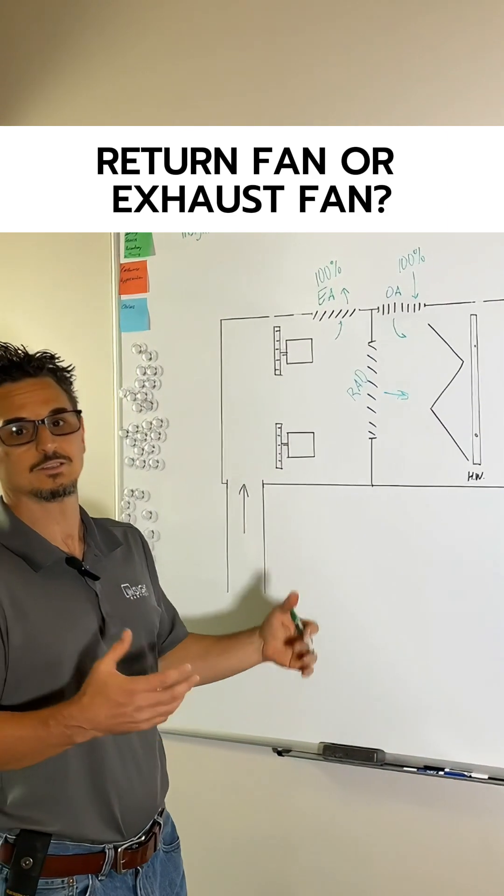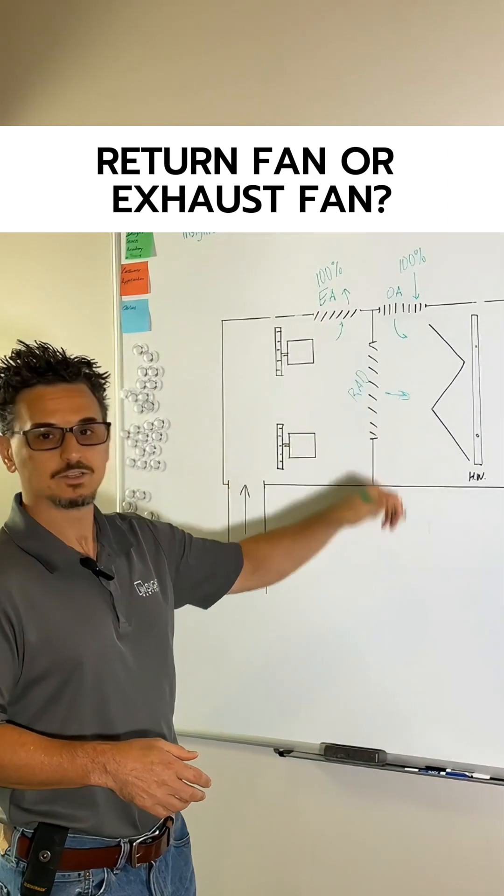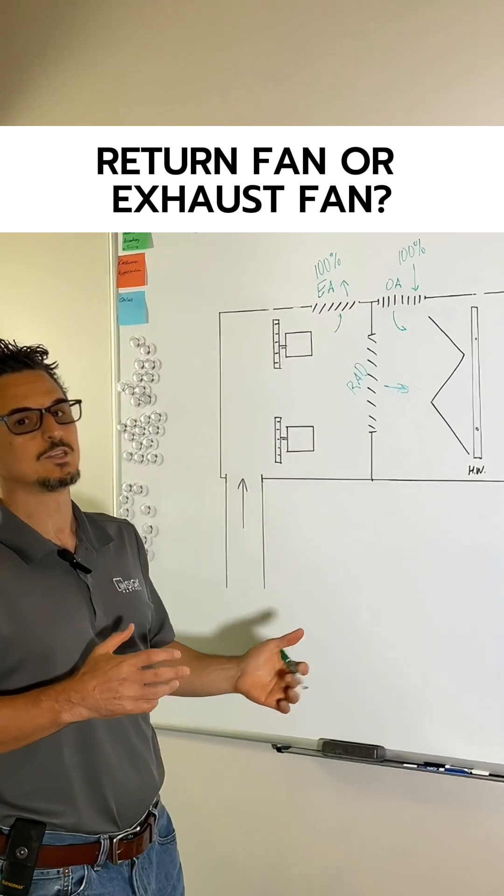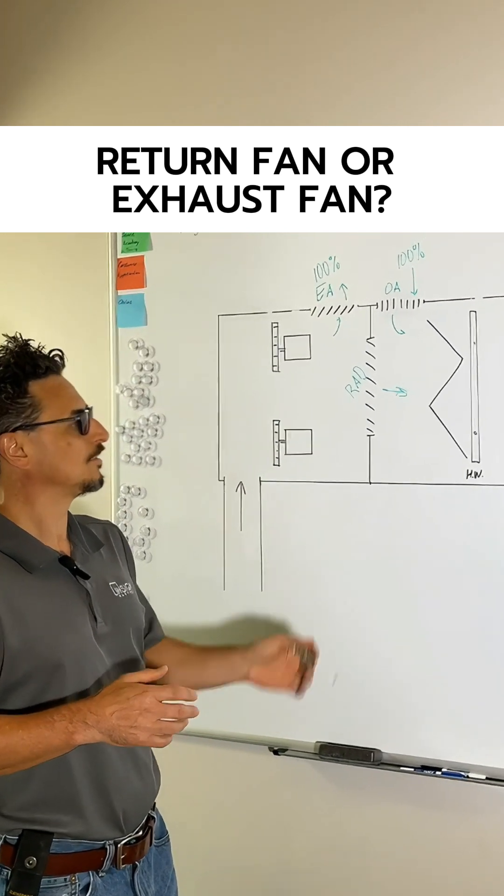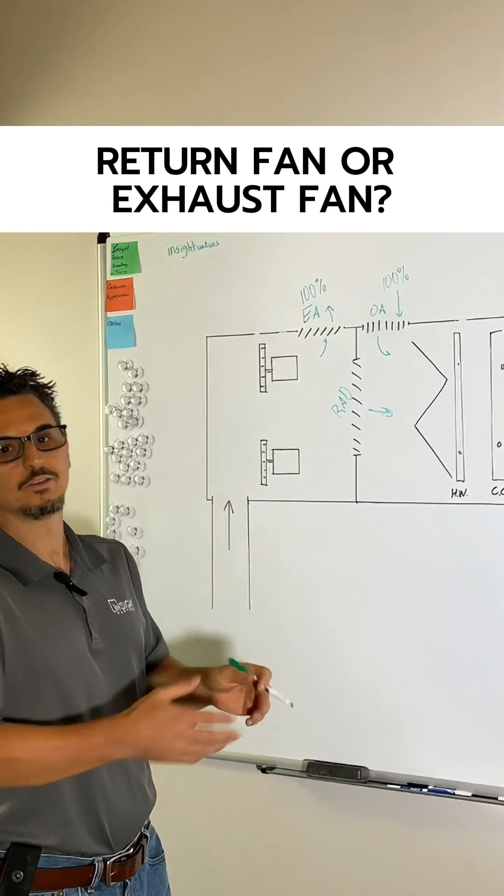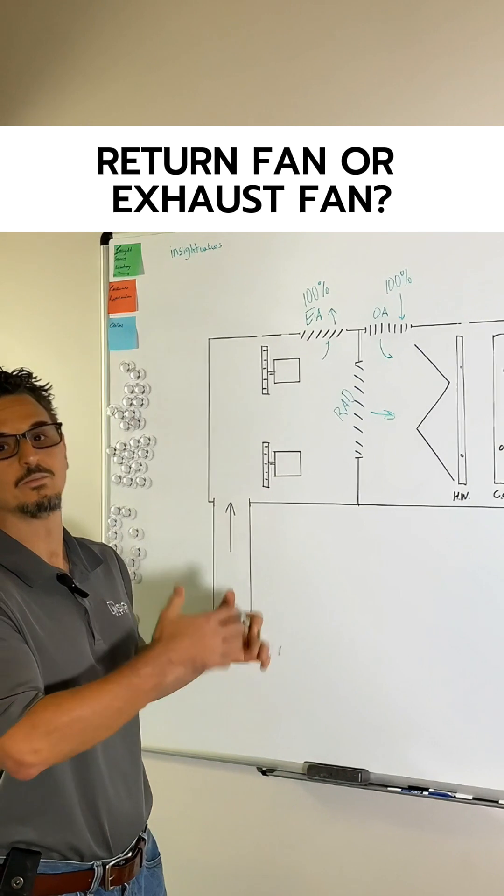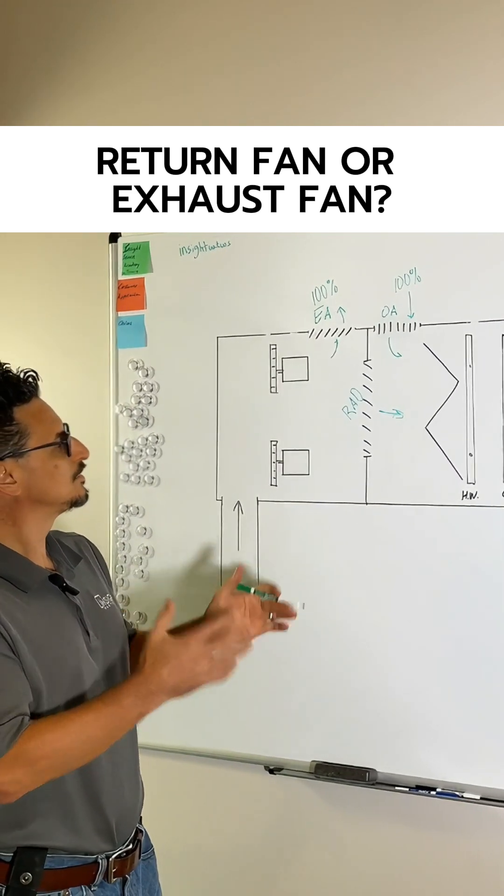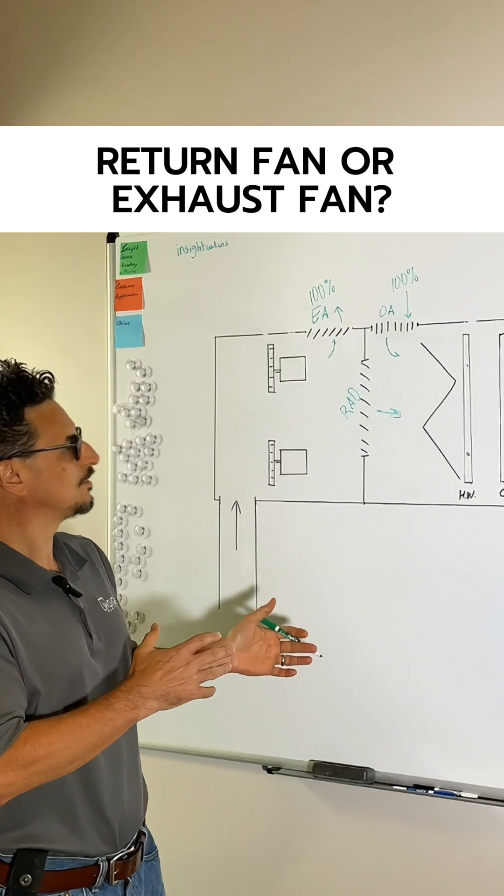Also allows you to break up the fan brake horsepower into two different banks, which is nice because you can imagine if you had a 20,000 CFM unit and you have 12-inch filters in here, you know, and it's a five-story building, you can imagine how much static pressure you're getting built up in that system. So it's nice to break up the fan horsepower into smaller increments. It's easier for maintenance and it's more efficient when you do that. So we talked about building pressure, we talked about efficiency, we talked about economizer.